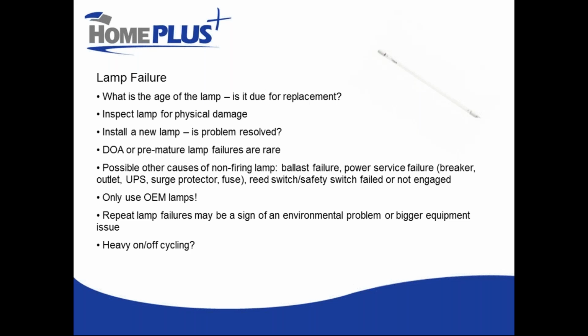And a lot of the UV systems these days have fail-safe mechanisms put in place so that you cannot fire the lamp without the lamp harness properly installed and the lamp inside the chamber. Most of those have some sort of safety switch or reed switch. A reed switch is like a little magnetic switch that, when two things are in proximity, will activate the switch and allow power to flow to the lamp. Some of the time, those reed switches or safety switches have actually failed, or they're not properly engaged, so it's not letting you fire the lamp simply because it wouldn't be safe to do so. A lot of the UV system controllers will have some sort of indicator to let you know that that is likely a problem, or point you in the right direction at least.